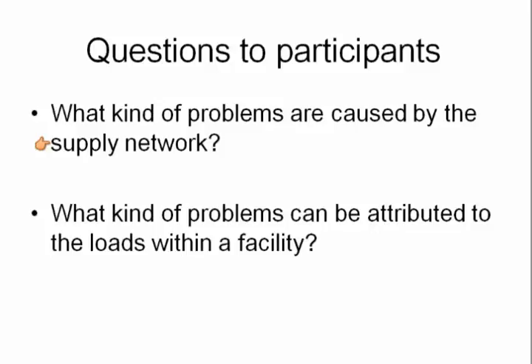Okay. And what kind of problems are attributed to loads within a facility? Within a factory, you have various loads. What kind of problems? Harmonics, if you have electronic equipment. Lower power factor, for example, if you have too many inductive loads. Starting of heavy loads, very good point, where a motor without a soft starter or a VSD can draw a large current, which can cause voltage drop. Good.